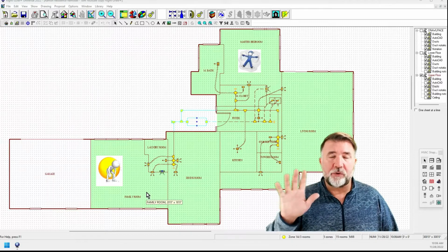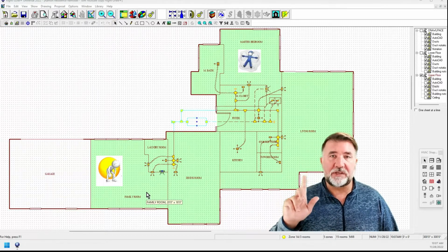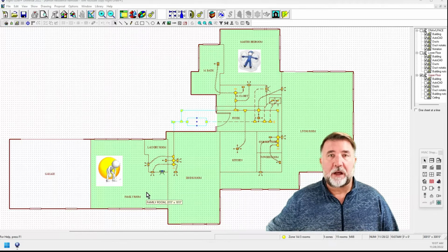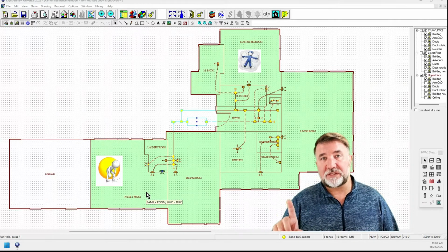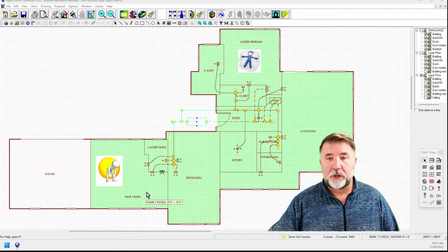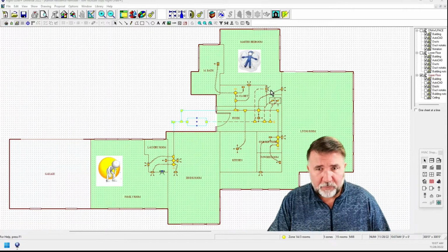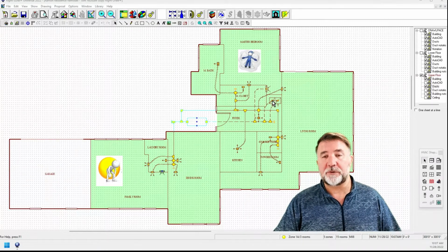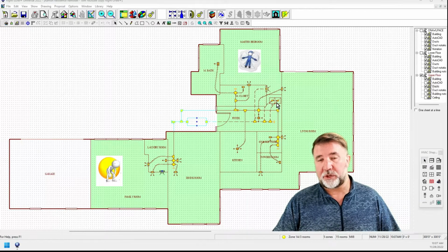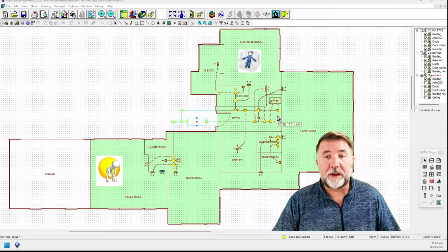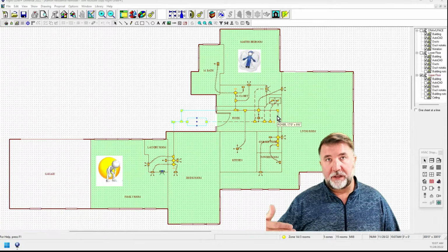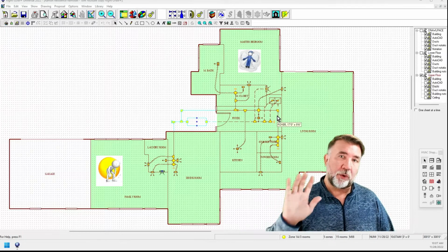So oversizing the air conditioning system is one of the biggest reasons that you have hot and cold spots in your house. Okay. And the second biggest issue is returns. So we talked about these returns over here, and notice that we have this return in the bedroom because there's going to be a door here on the master bedroom. So when that door closes, I'm not able to get the ability of these returns to pull that air out of the room. And that's why in most states, it's mandatory that a return be put in a room that has a door that can be closed off.